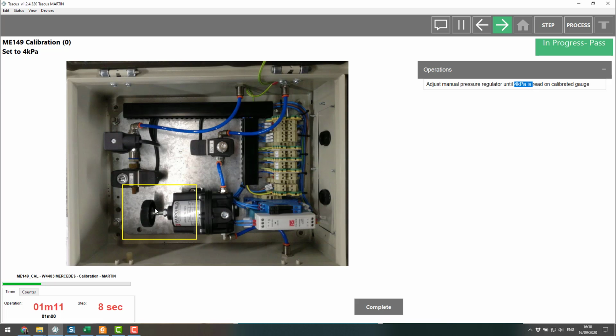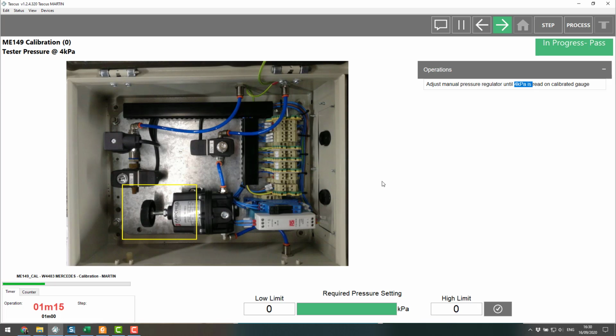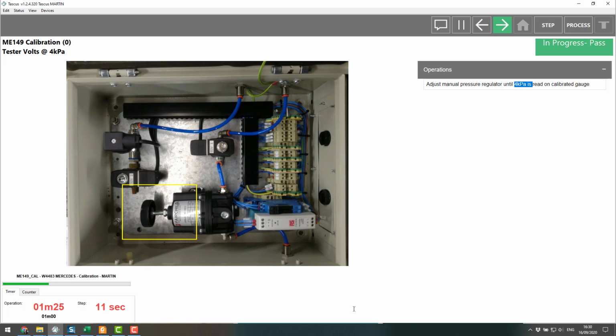So it's saying to begin with, adjust the regulator to 4. So I'll do that and then I take a measurement on the gauge and see what that returns. So it's saying I've adjusted it to 4 kilopascals and I'm reading 4 on the test equipment. Then it's asking me to read what the voltage is. So I'll have a look on the tester screen and that's 3.95 volts. So we'll go through this. Asking me to capture these values.